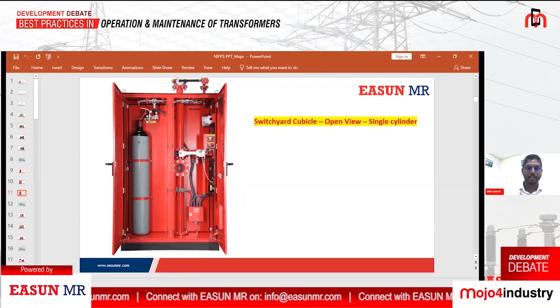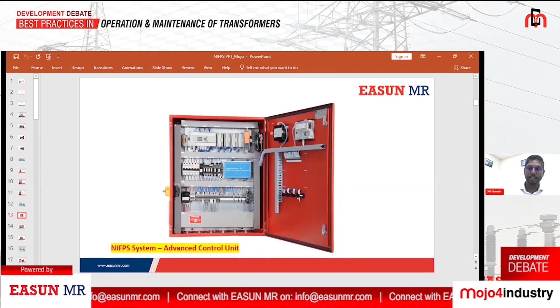And this is an advanced control unit. If there is some fire possibility in a transformer, the sensor which we have fitted in the transformer gives a command to this system. This system will be placed in the control room, and it gives a command to the field-installed nitrogen cubicle systems to operate and to inject nitrogen. This is a control system which would be placed in a control room.